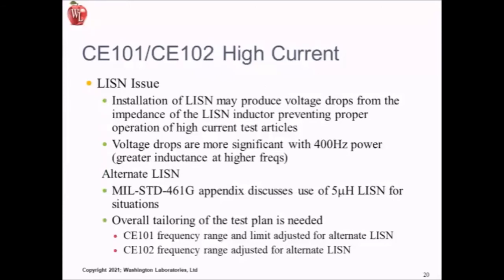So one of the things that we have when we set up our emissions testing, we have LISNs, or line impedance stabilization networks, in line. You have to be careful with the current rating on those things. You have to be mindful of that. Make sure that you have the right LISN rating so you don't have unwanted voltage drops, because in line with the LISN, there's an inductor right there. So if you have a high current draw, you could actually drop the operating voltage. So be mindful of that.